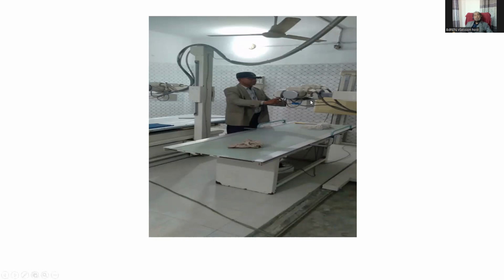So next time I will show the generator, how to control the tube, how to take the high voltage tank, everything. An X-ray machine consists of some major parts, such as the control box or control panel and the high voltage tank, which is known as the generator, that we use with an inverter circuit. That means first 220 volts is given, then the high voltage generator generates high voltage including high frequency.